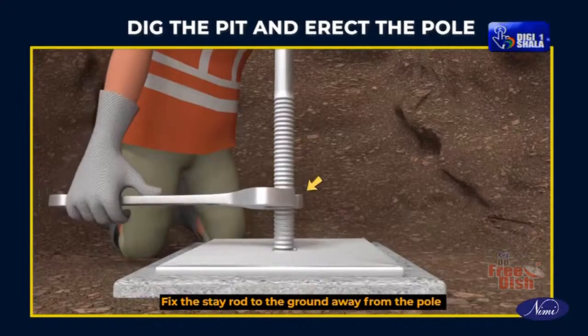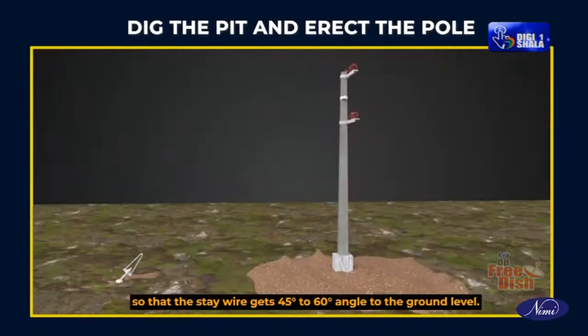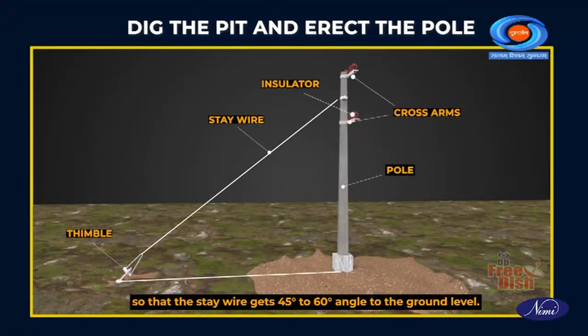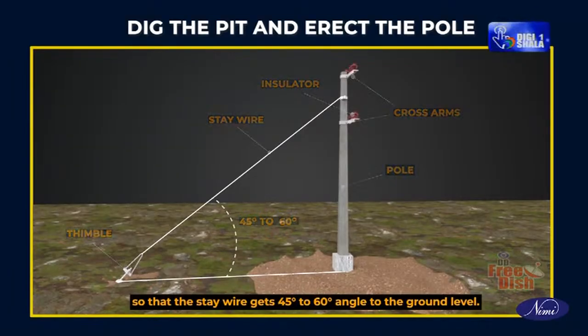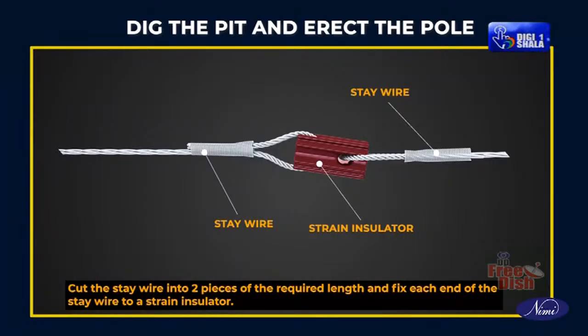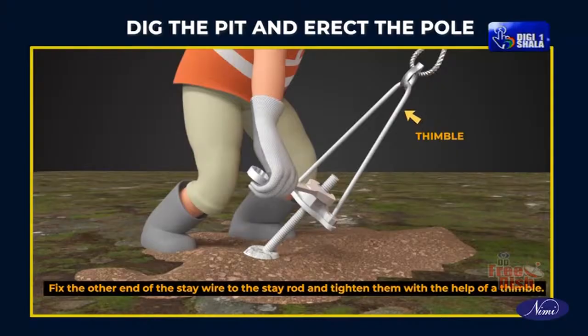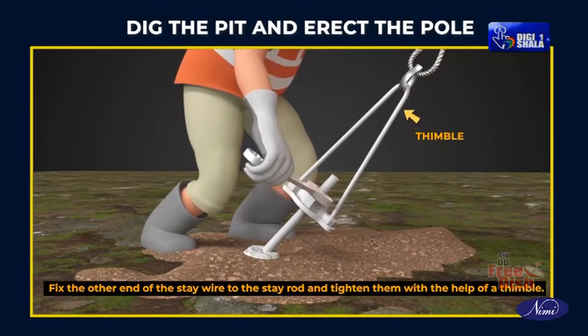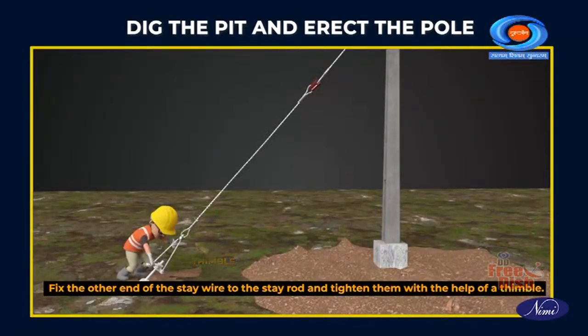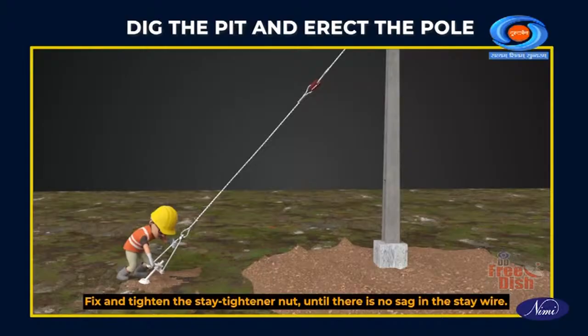Fix the stay rod to the ground away from the pole so that the stay wire gets 45 degrees to 60 degrees angle to the ground level. Cut the stay wire into 2 pieces of the required length and fix each end of the stay wire to a strain insulator. Fix the other end of the stay wire to the stay rod and tighten them with the help of a thimble. Fix and tighten the stay tightener nut until there is no sag in the stay wire.